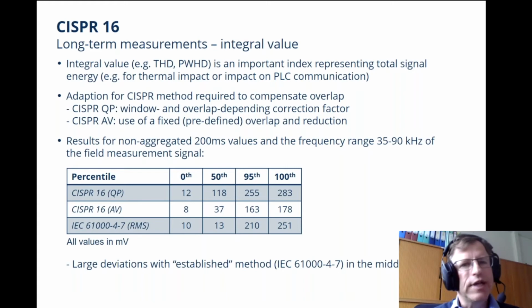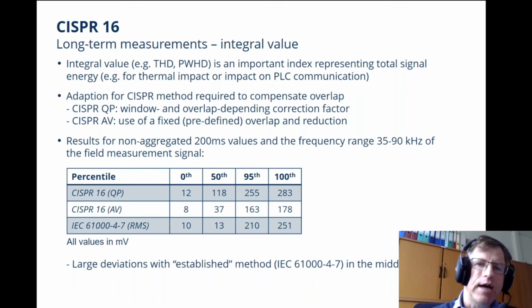So this sounds to me also somehow experimental, and not really thorough, systematically proven. But at least it should work for most of the equipment. And if you now apply those integral values, these adapted CISPR methods, and compare them with the established value that we usually use today, which is based on the 4-7 method, you see that in the unaggregated 200 millisecond values, if you do statistical analysis, there are quite a lot of differences, with the 4-7 method being in the middle.